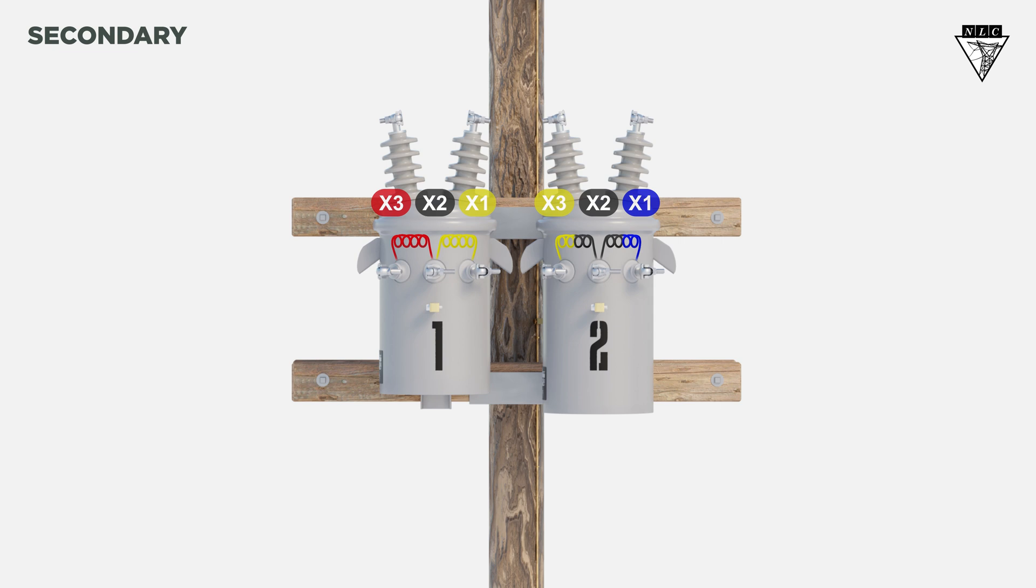To complete the secondary side, first, bond all transformer cases together and tie them to ground. Use the lighting transformer's X2 bushing as the neutral.